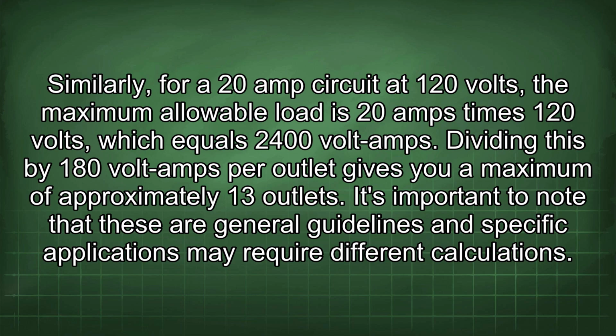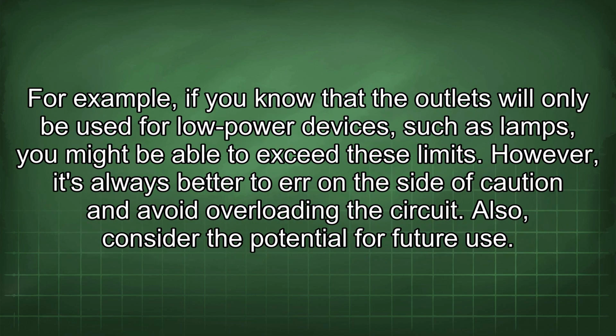Similarly, for a 20 amp circuit at 120 volts, the maximum allowable load is 20 amps times 120 volts, which equals 2400 volt-amps. Dividing this by 180 volt-amps per outlet gives you a maximum of approximately 13 outlets. It's important to note that these are general guidelines and specific applications may require different calculations. For example, if you know that the outlets will only be used for low-power devices, such as lamps, you might be able to exceed these limits. However, it's always better to err on the side of caution and avoid overloading the circuit.